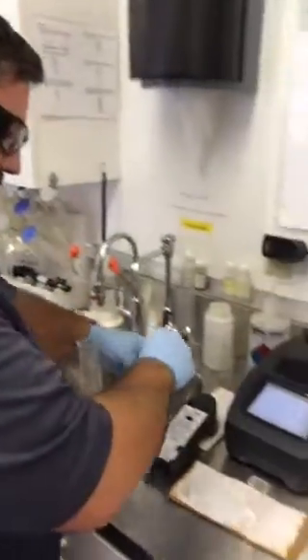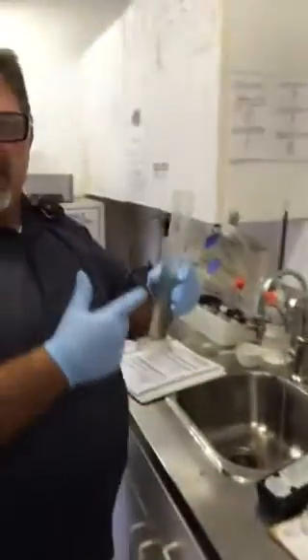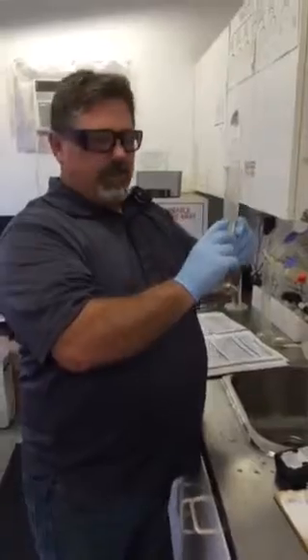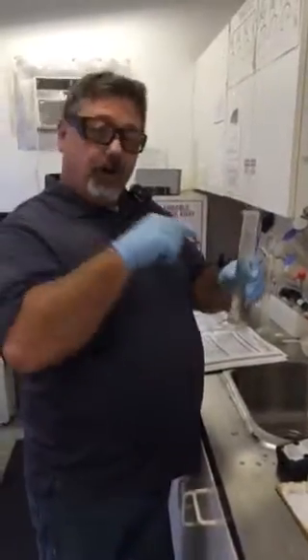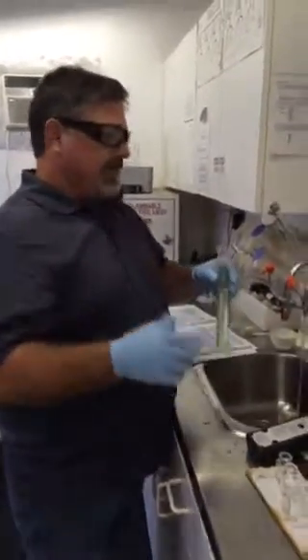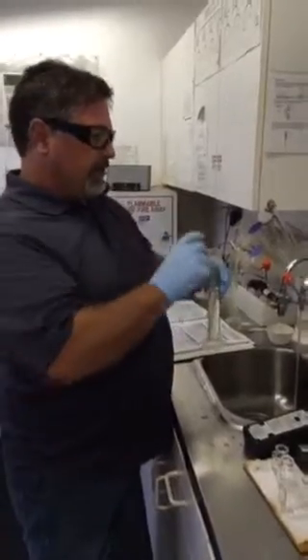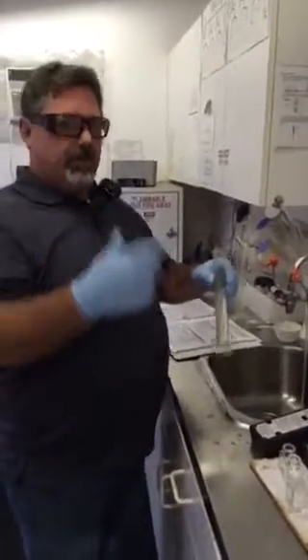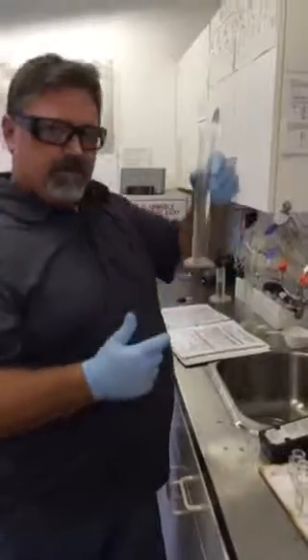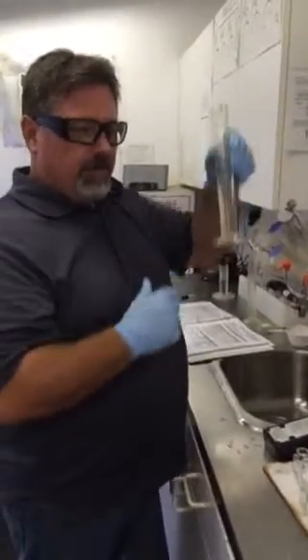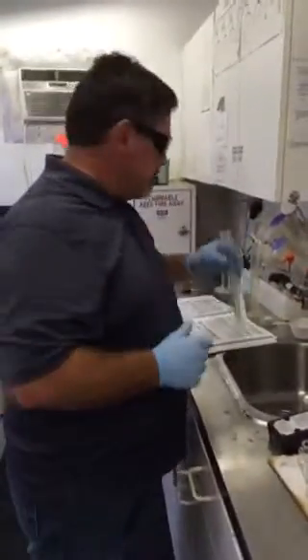Okay. The good thing about doing this test is also remember you have your dilution in here. This is a good sample to use for your hardness test. And then that way you're not doing a crazy sample trying to get up to a 1,000 ppm hardness. You already have a diluted test for your cooling tower. You can use this for your cooling tower hardness test as well.